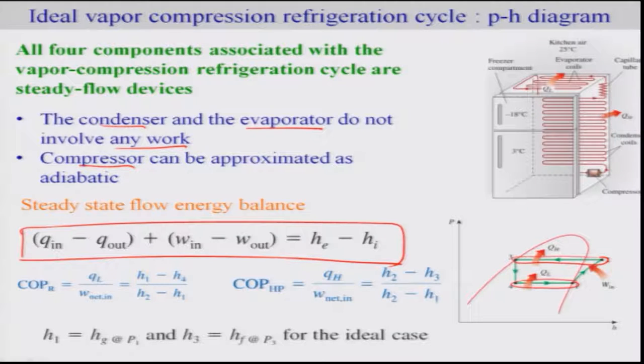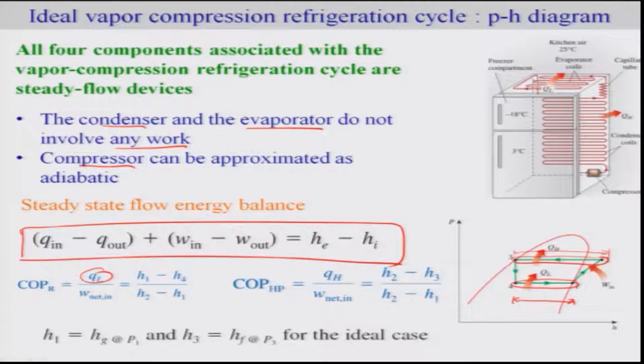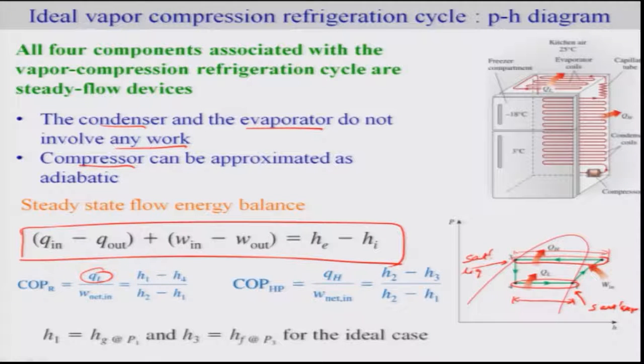Using this, one can find the COP_R: Q_L equals H1 minus H4, and W_net equals the enthalpy change across the compressor, which is H2 minus H1. Similarly, COP_HP gives Q_H as H2 minus H3, divided by W_net. For ideal conditions, the refrigerant is saturated vapor before entering the compressor and saturated liquid after the condenser. Thus H1 equals H_g at P1, and H3 equals H_f at P3.